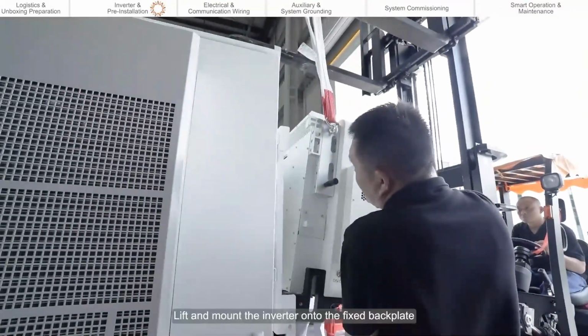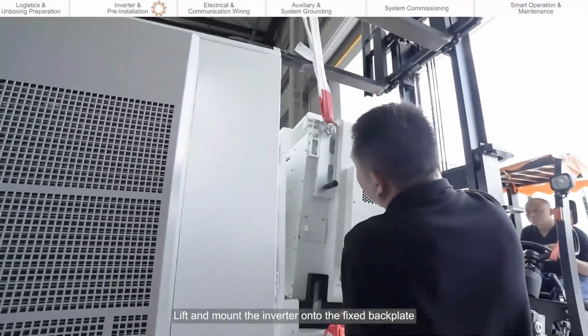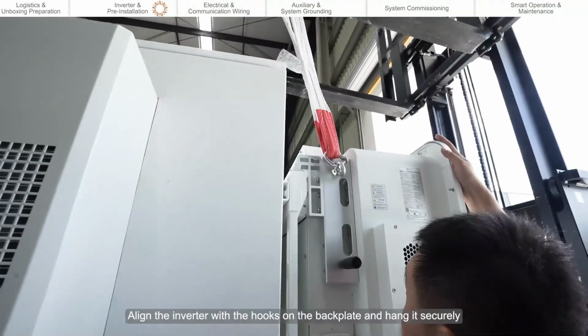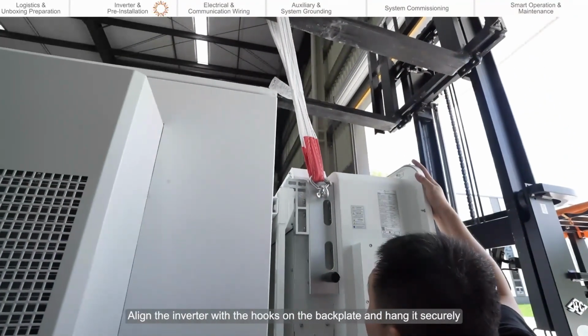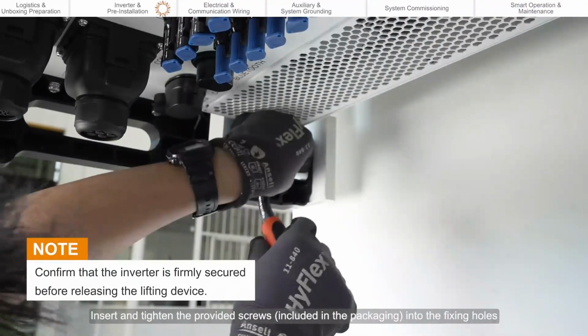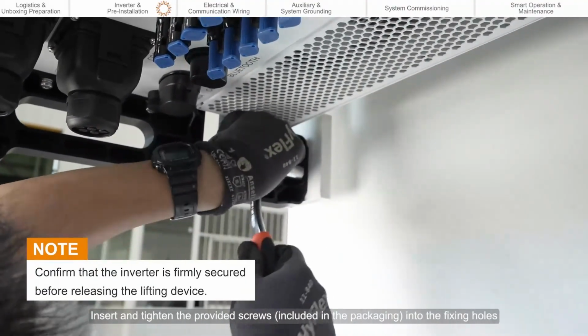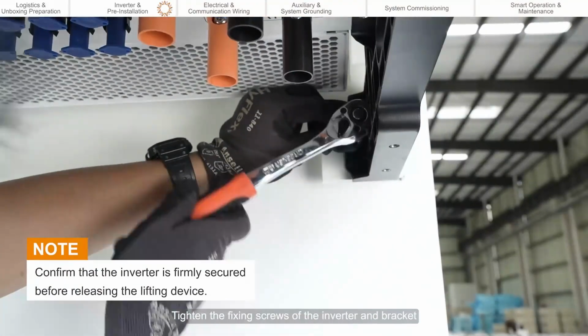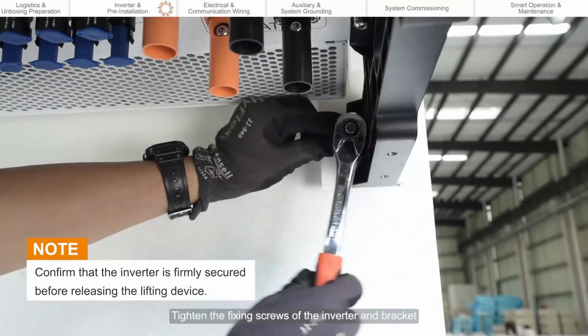Installation positioning. Lift and mount the inverter onto the fixed backplate. Align the inverter with the hooks on the backplate and hang it securely. Insert and tighten the provided screws, included in the packaging, into the fixing holes. Tighten the fixing screws of the inverter and bracket.